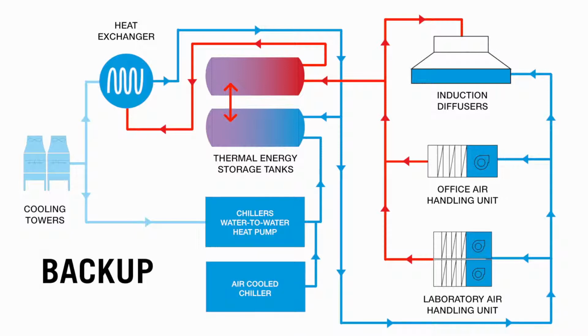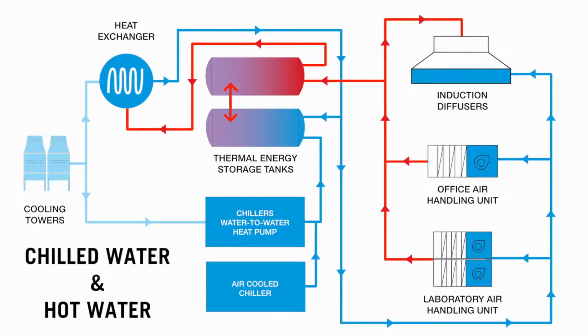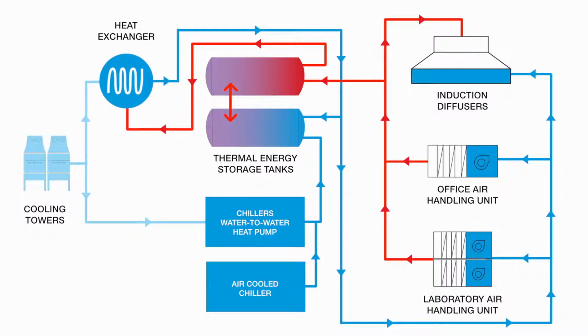We do have an air-cooled chiller as a backup to the system, and typically the water-to-water heat pump, when it's running, if we're not using the cooling tower and during certain times of the year, we can actually make hot water on the other side of that heat pump. So that heat pump can make chilled water and hot water simultaneously. So if we think about a spring day or a fall day where we might need a little bit of heat in the morning and then cold water or cooling in the afternoon, that water-to-water heat pump can provide both.